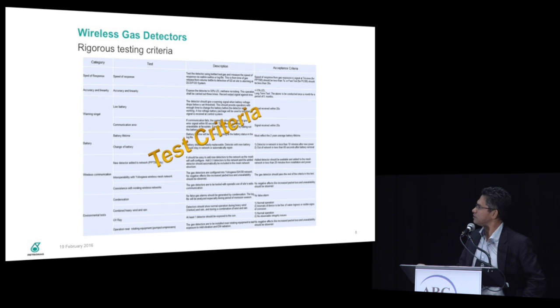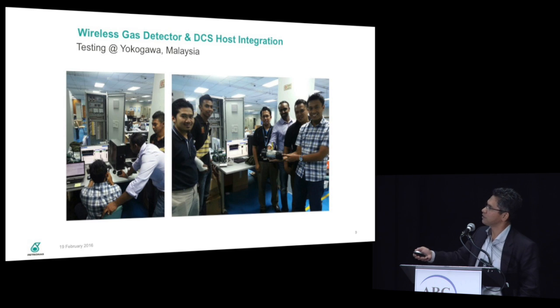So we have these test criteria, for example the speed of response, accuracy, the low battery alarm, the communication errors, the battery lifetime, and whenever there is heavy rain, what happens? There are a lot of acceptance criteria that we rigorously go through to make sure that the installation is successful, and they have passed all these tests. Upon passing all these tests, then we proceed. And this is the team that did the test in Malaysia, in the Yokogawa office in Malaysia.